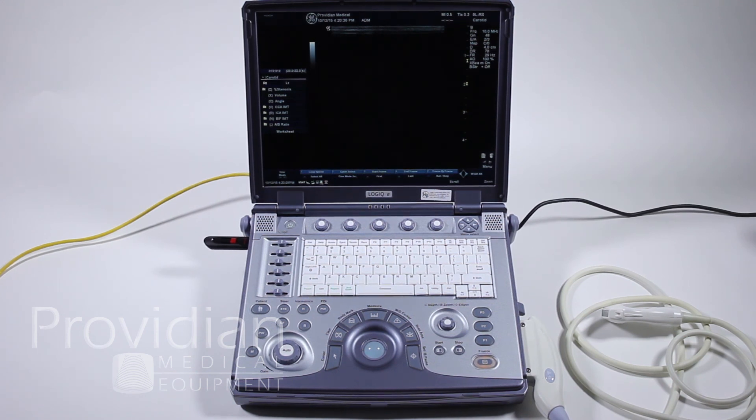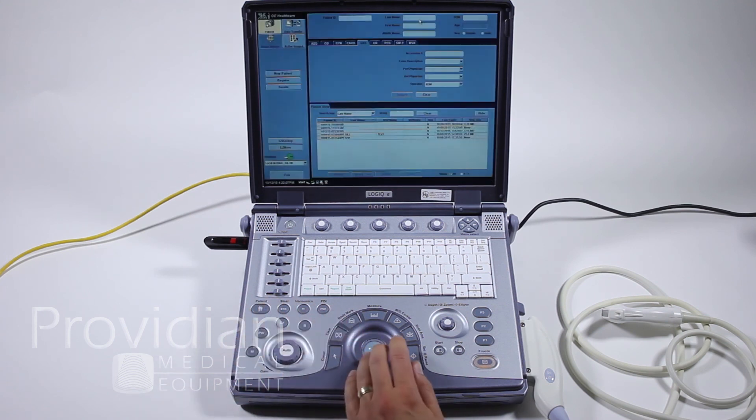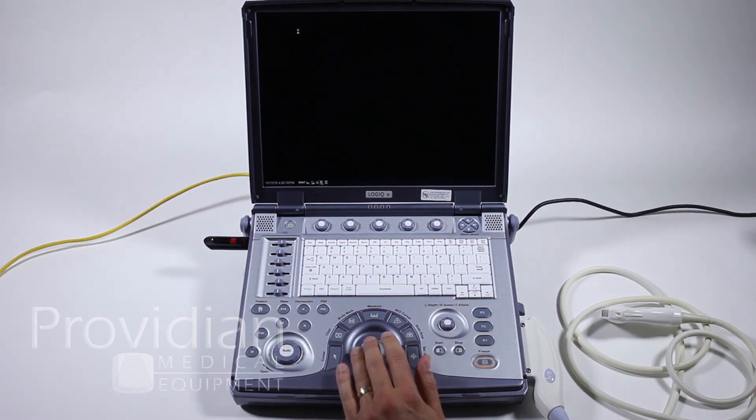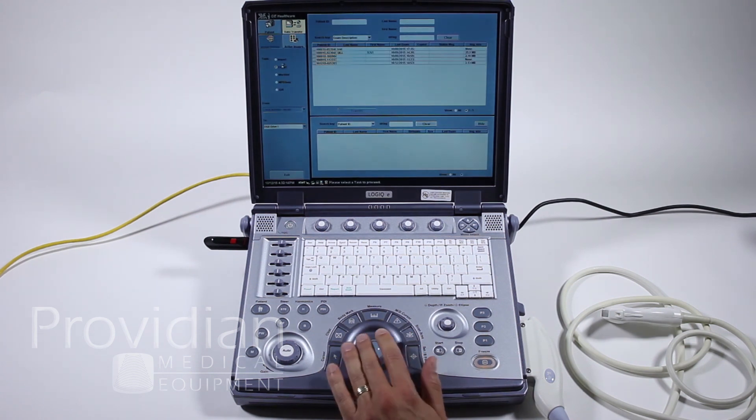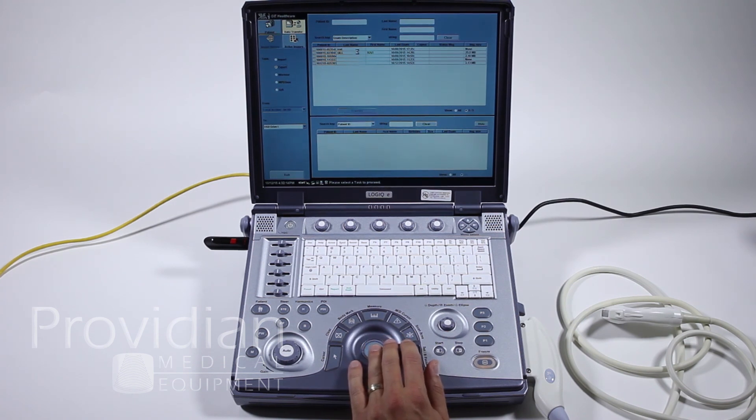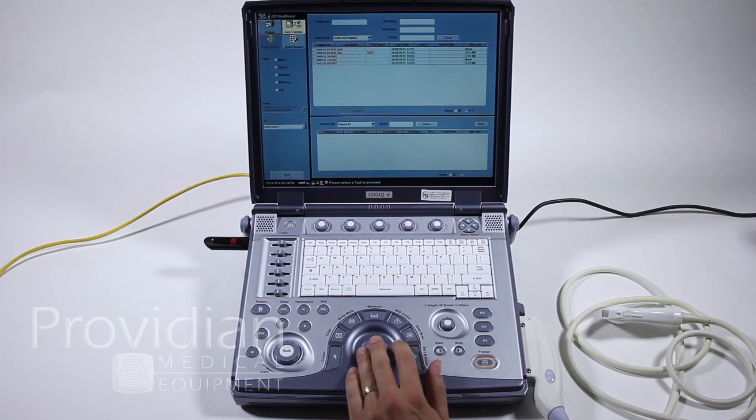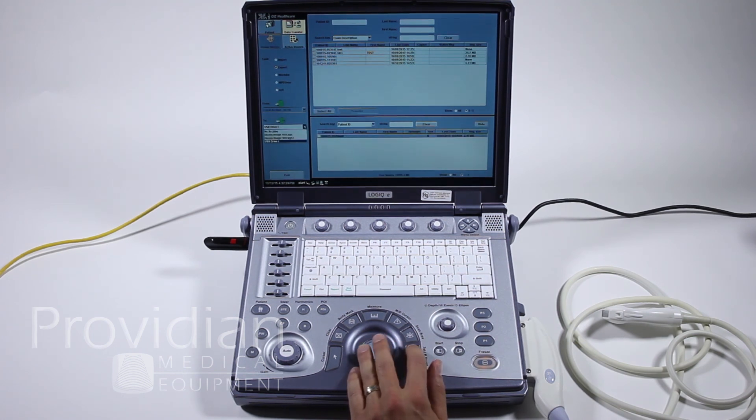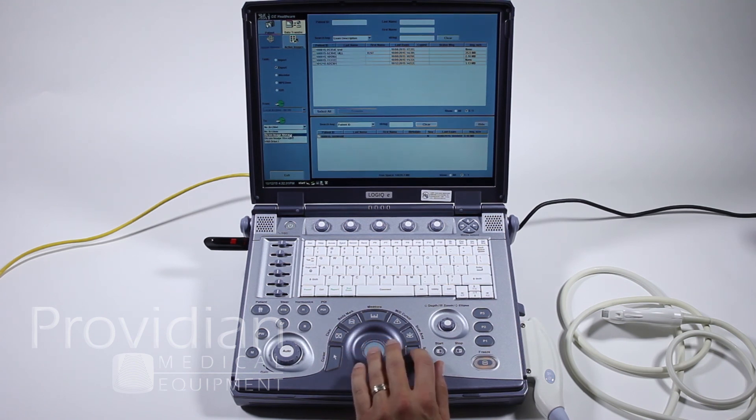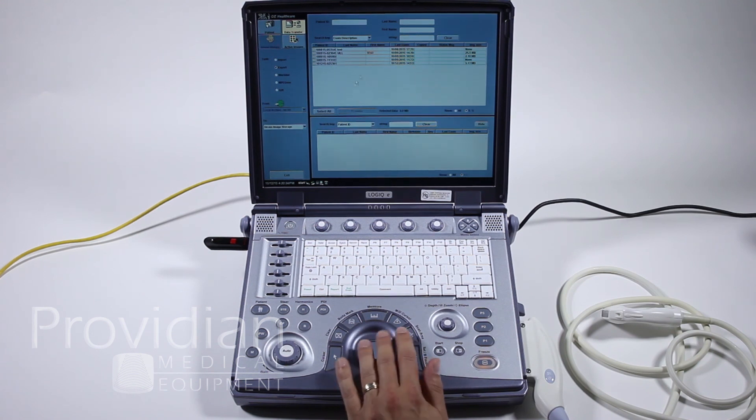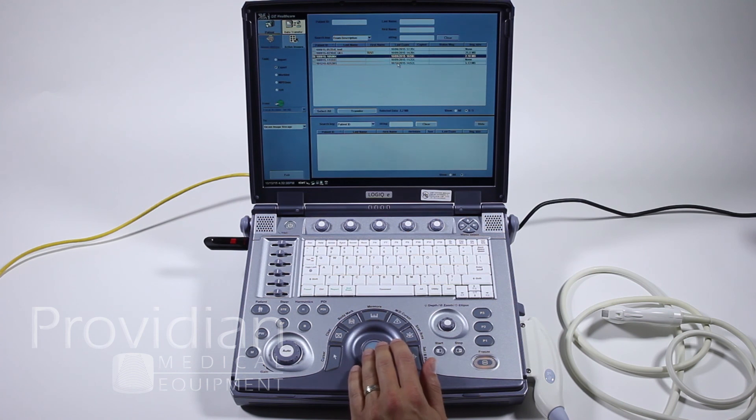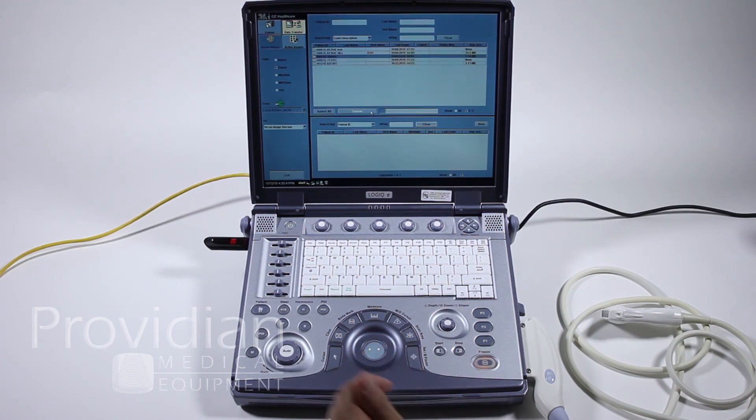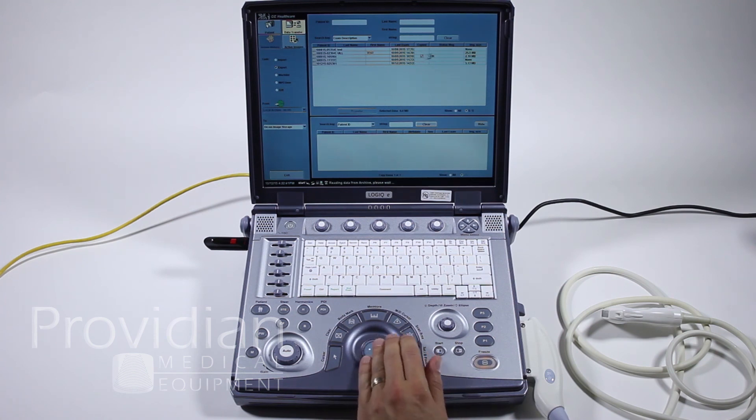Let's show how to send it to the DICOM network. We'll click the patient. We did go through this briefly. Data transfer, I'm going to go ahead and choose Export over here on the left-hand side. Let me first select the location. I'm going to choose this DICOM image storage. See this DICOM image storage 2 appeared. I can click DICOM image storage. This is saying it's going to go to my DICOM server that I have set up. I'm going to choose this smaller file with 2 megabytes. I'll go ahead and click Transfer. There, it shows that it just transferred over the network, and the status is OK.